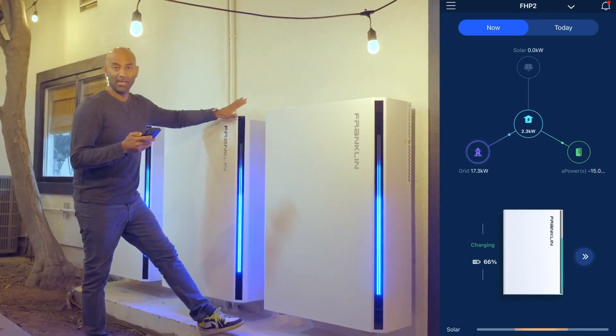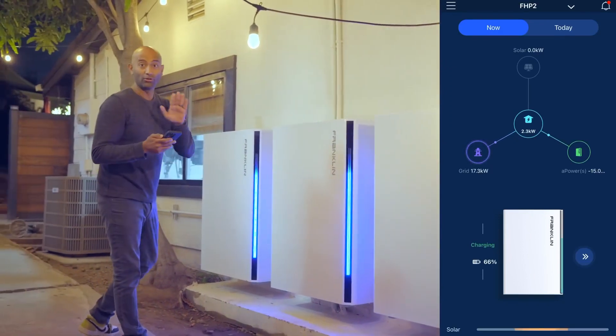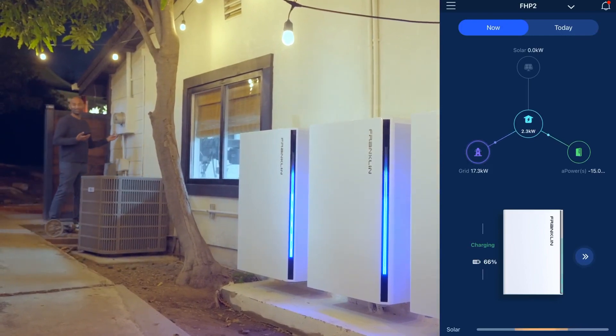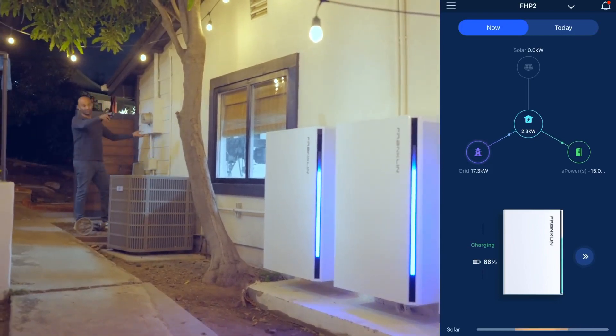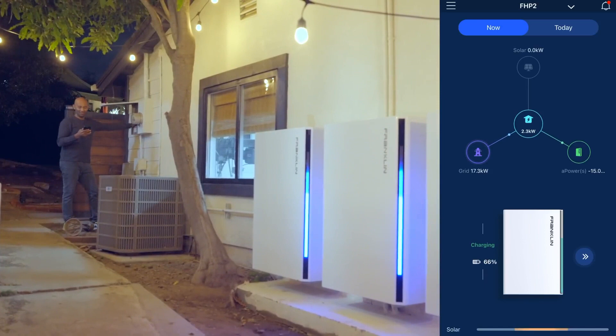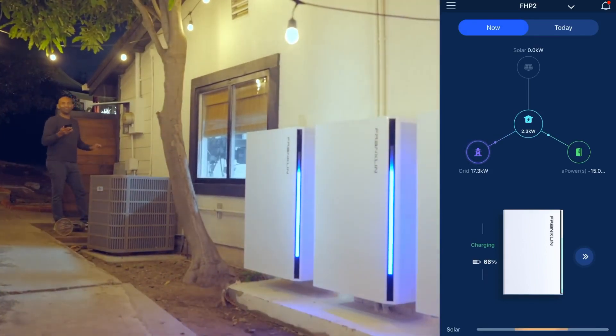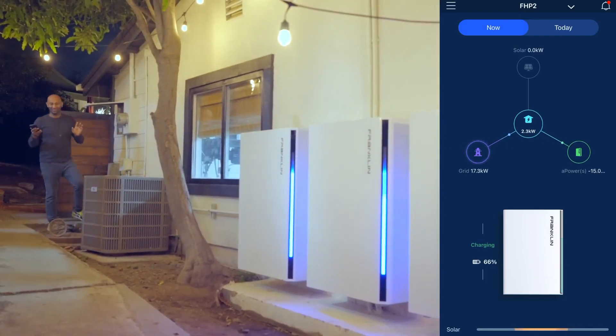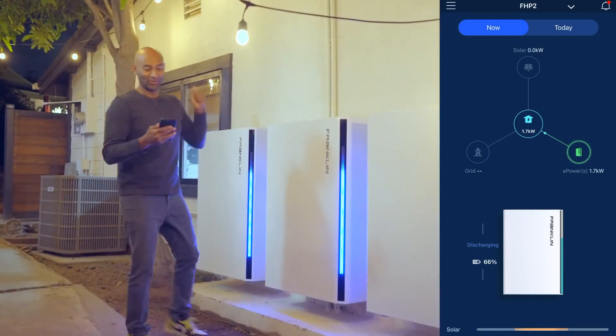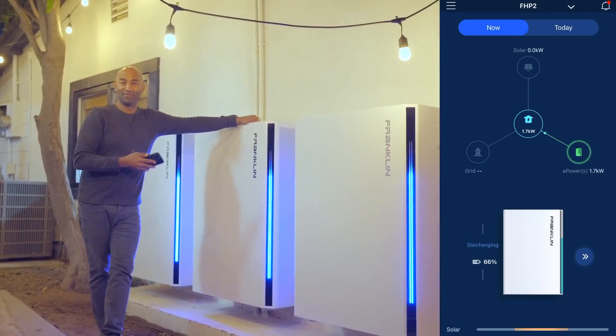Now let's see what happens when we're in emergency backup mode. Right now the batteries are on, but the house is running on grid. I am going to disconnect. I'm checking for the lights — inside the garage, those lights up there. Let's see how much of a flicker there is. One, two, three. Is that a little bit of a flicker? Maybe a little? Now the grid is off. You can see here it tells you there's no grid and we are running the house from the batteries.